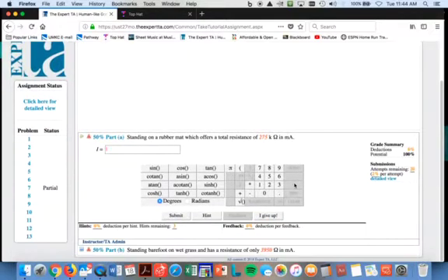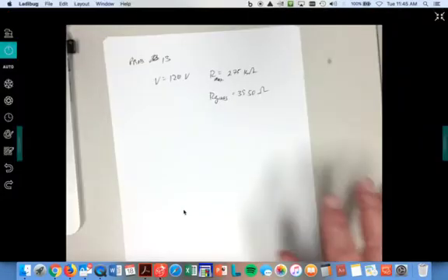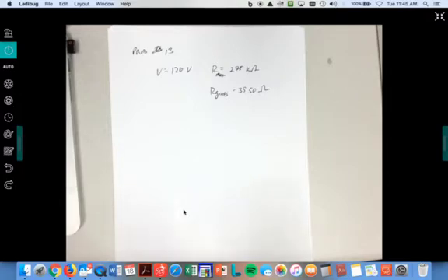And then again, the resistance drops quite a bit in the wet grass. So this is R for the mat, R for the grass, and you'll see all this in a minute. R for the grass is equal to 3950, just ohms in this case, or 3.9 kilo ohms. All right, so let's look and see what I've got written down here. Whoop, wrong thing. Okay, so this isn't hard.